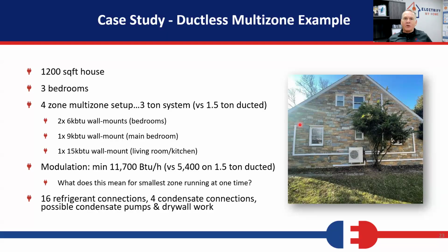So, in this particular application, it's 3 bedrooms. So they're doing a 4 zone multi-zone setup, a 3 ton system. And they could have done in that same house a 1.5 ton ducted system. So they put a 3 ton in, a system that's twice as large as it needs to be. They put two 6,000 BTUs in the smaller bedrooms. The main bedroom got a 9, and the living room kitchen got a 15.